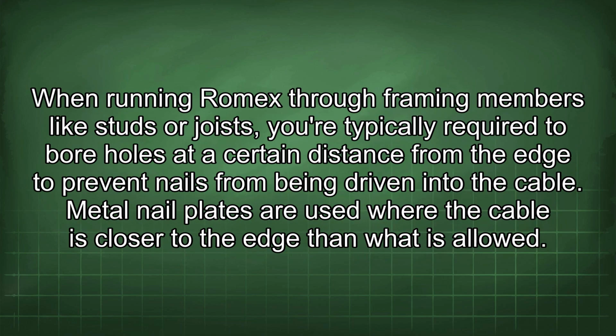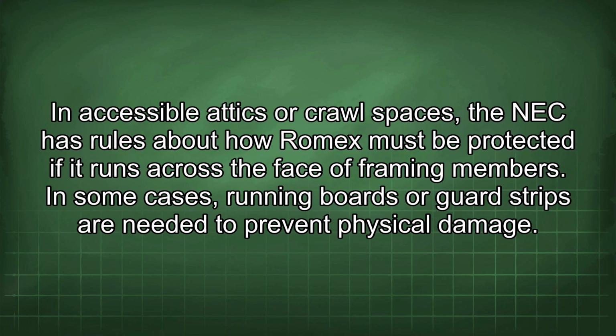When running Romex through framing members like studs or joists, you are typically required to bore holes at a certain distance from the edge to prevent nails from being driven into the cable. Metal nail plates are used where the cable is closer to the edge than what is allowed. In accessible attics or crawl spaces, the NEC has rules about how Romex must be protected if it runs across the face of framing members. In some cases, running boards or guard strips are needed to prevent physical damage.